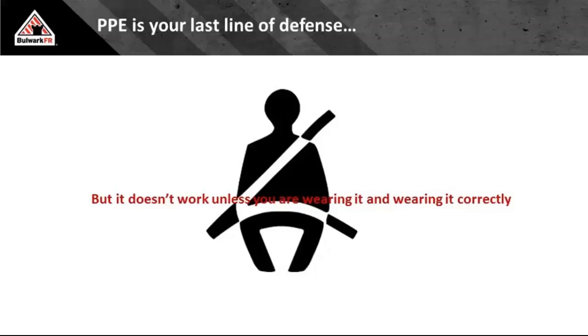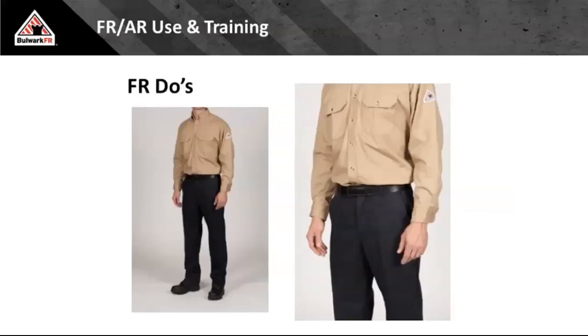I can have all the correct PPE. I can have the best fall harness in the world. If it's not cinched up correctly, if it's not secured properly, if my D-ring's not attached to my fall protection, it's not going to protect me the way I need it. And your arc-rated flame-resistant clothing is no different. If I am not deploying it correctly, or worst case, I don't even have it when I need it, how well can it protect me?